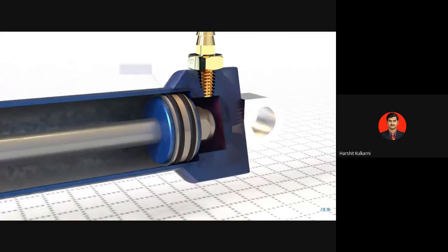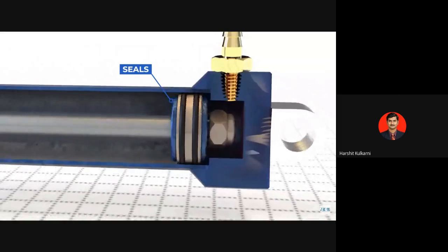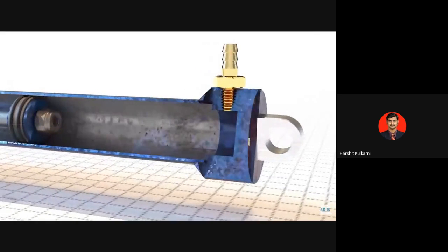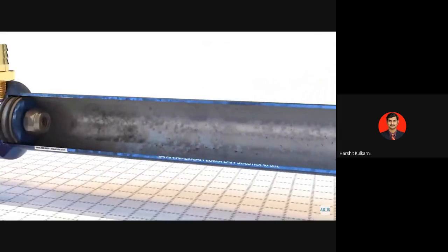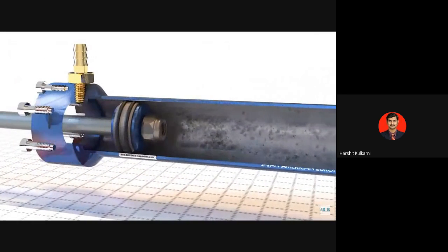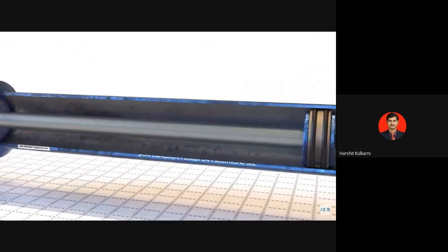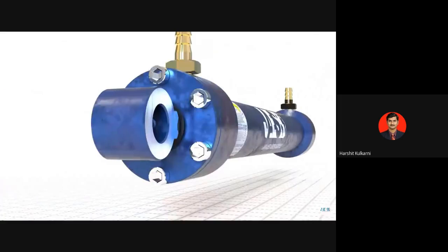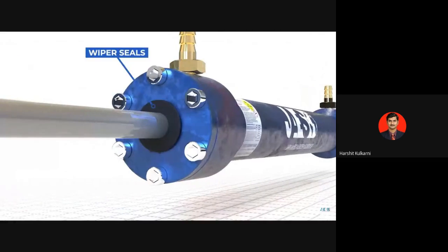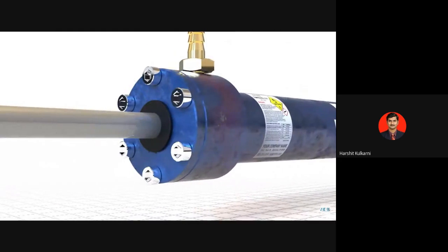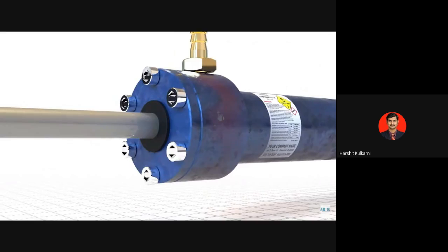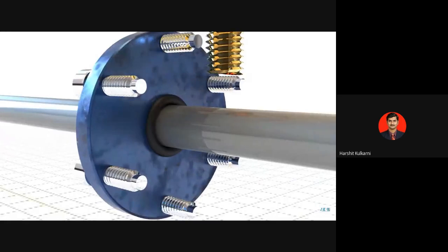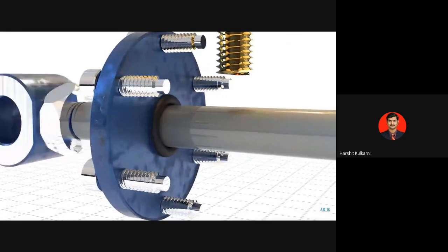A set of circular sealing rings are used in the interface of metals. The seals used between the surface of the metals in relative motion are dynamic seals, and those acting between 2 surfaces at rest with respect to each other are static seals. A piston seal acts as a pressure barrier between 2 chambers separated by a piston. The seal is used to wipe dirt from the rod while entering through the head and prevent contamination of oil. A rod guide ring is used to absorb transverse forces acting on the system and prevents metal to metal contact of the rod and cylinder head.